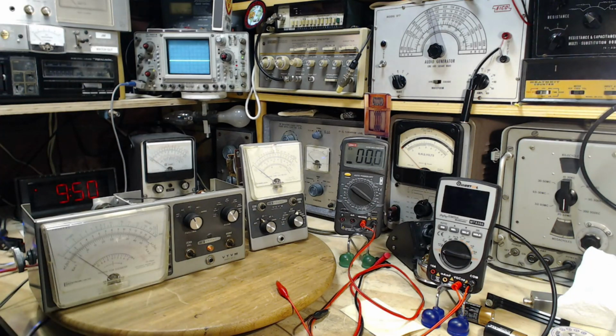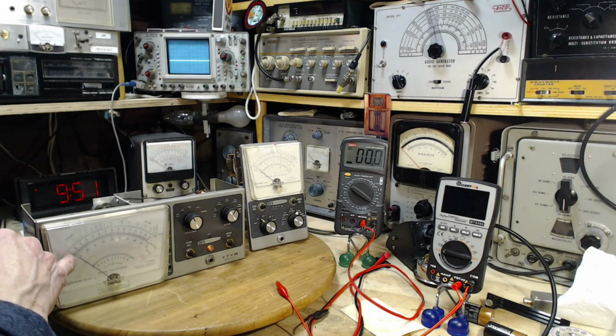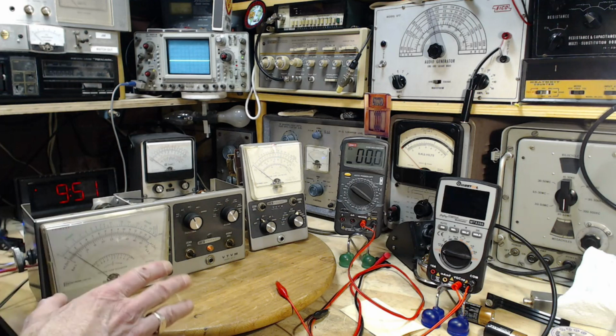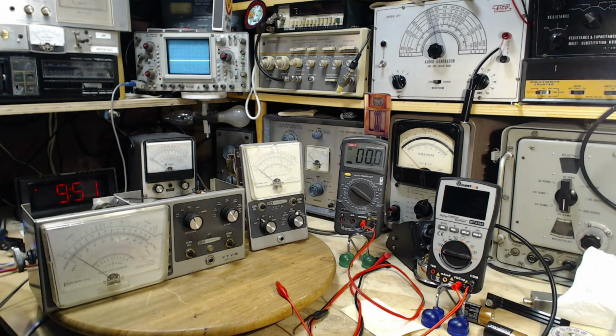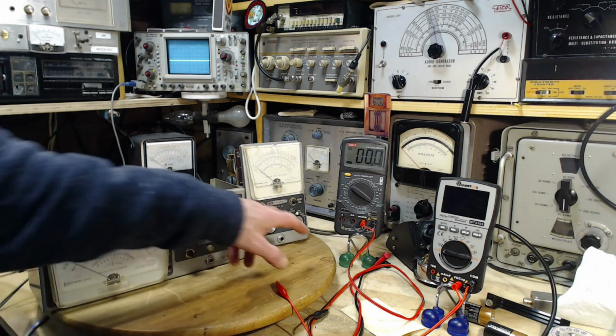Calibration. So the very first step in calibration is simply to make sure the pointer sits on 0. It's not sitting on 0 now when the units are switched on, so let's switch them off and we'll adjust the mechanical balance in the meter itself.